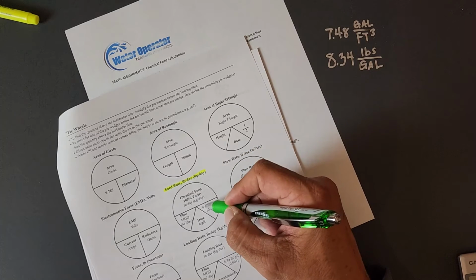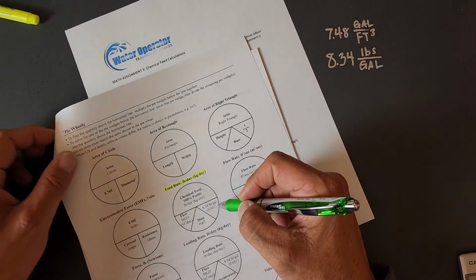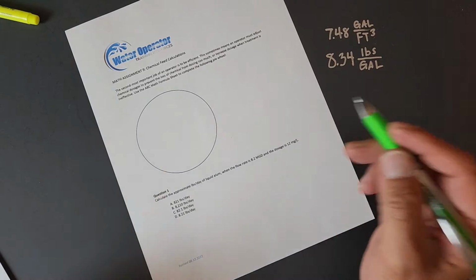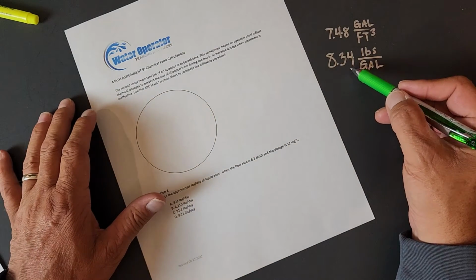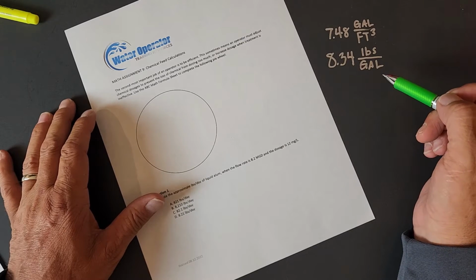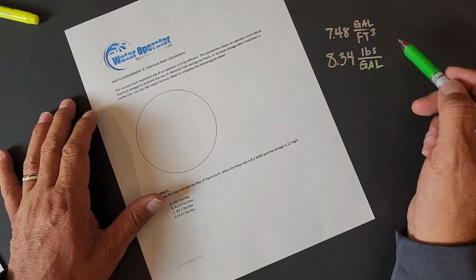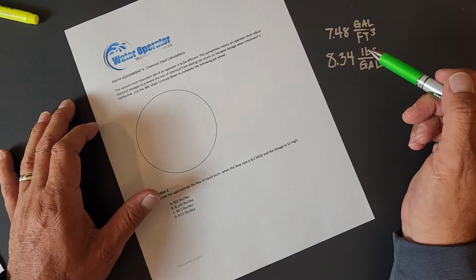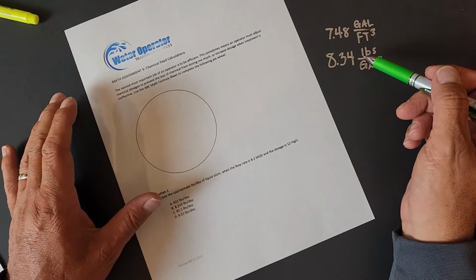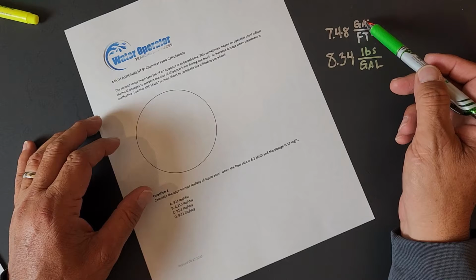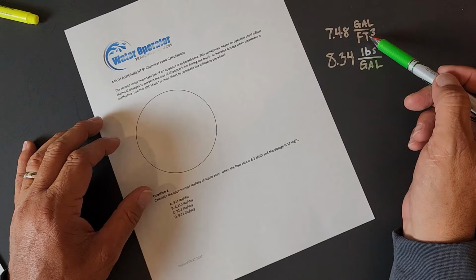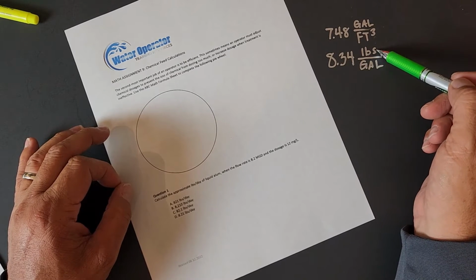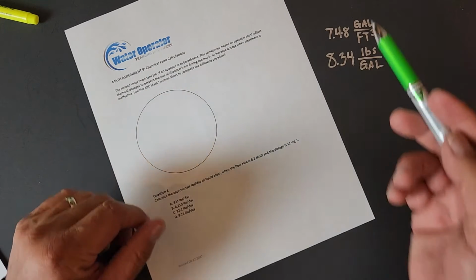This last piece of the pie is 8.34 pounds per gallon. That's always going to be that, 8.34 pounds per gallon. You'll see on my desk here that I've written down 8.34 pounds per gallon. Just like 7.48 gallons per cubic foot, it's important that every operator is familiar with this. When you walk in the door or the front gate to your plant in the morning, you should know that there are 7.48 gallons for every cubic foot. You should know that water weighs 8.34 pounds per gallon. These are things that we should know.